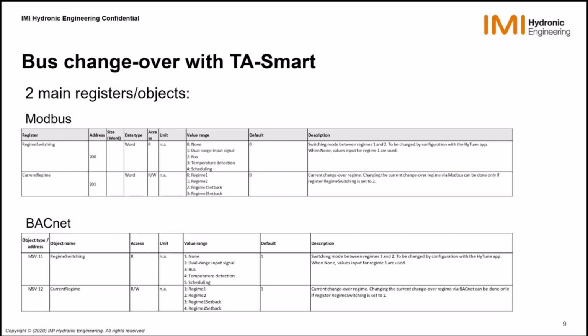But the 2 most important registers for the changeover itself: the first is the definition of the regime switching. It defines whether the regime switching is 0, none; 1, dual range; 2, bus; 3, temperature detection; 4, scheduling, which is not yet implemented. This one is read-only. You need to set it up with the app because you have a lot of parameters to set, and that would be much too difficult to do entirely by the bus. So you do this only once. But then switching between the regimes is done through the register current regime, where you can set the current regime to a value of 0 or 1, regime 1 or regime 2.